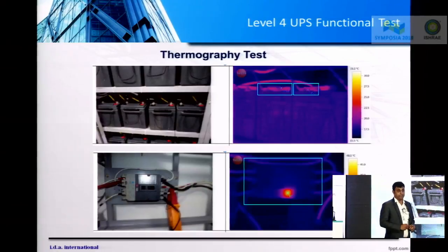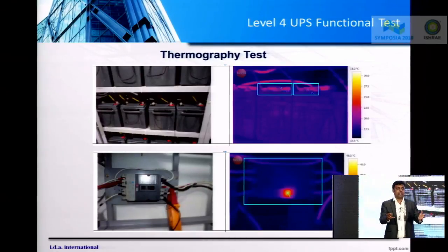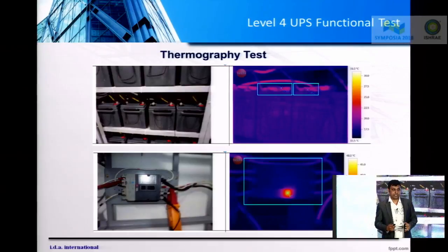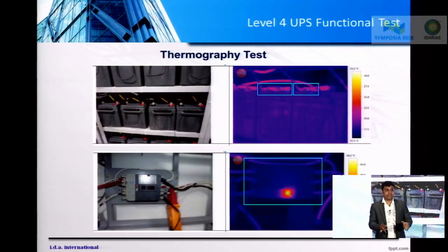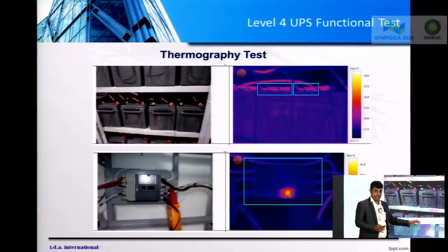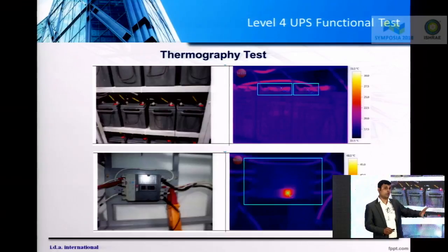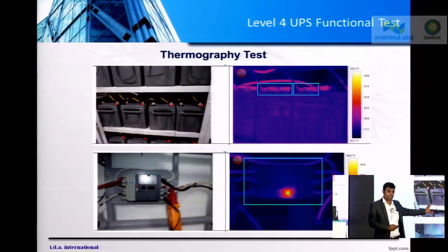Finally, thermography. When you are loading a particular equipment to its full load condition, and if there are any loose links, it will get identified through a thermography test. Or when you are doing a UPS battery discharge test, it is very important to verify the temperature or thermal conditions of the battery during the discharge conditions.